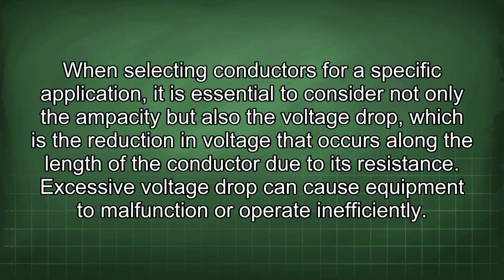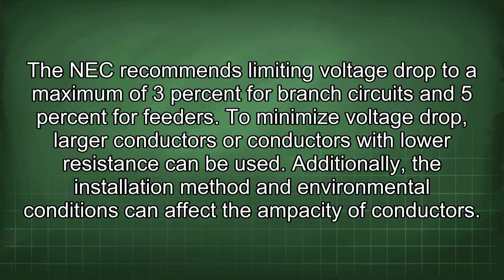When selecting conductors for a specific application, it is essential to consider not only the ampacity but also the voltage drop, which is the reduction in voltage that occurs along the length of the conductor due to its resistance. Excessive voltage drop can cause equipment to malfunction or operate inefficiently. The NEC recommends limiting voltage drop to a maximum of 3% for branch circuits and 5% for feeders. To minimize voltage drop, larger conductors or conductors with lower resistance can be used.